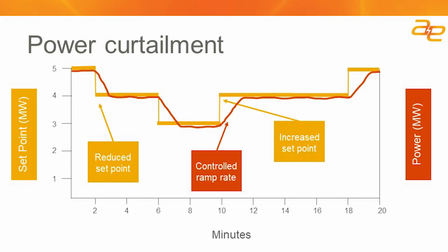So if we look at how this works in practice, we've got an output from a plant as measured by a power meter, which should correlate pretty closely with what the inverters themselves are reporting as their output. If we have a set point for the plant at 5 megawatts, the inverters are generally configured so that they can't go beyond 5 megawatts. They can only produce 5 megawatts of power coming out of the plant.